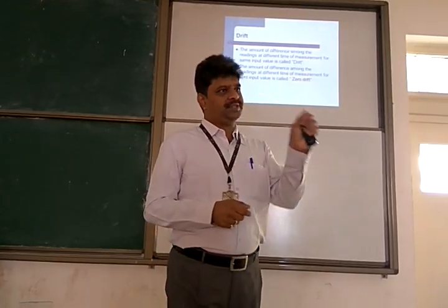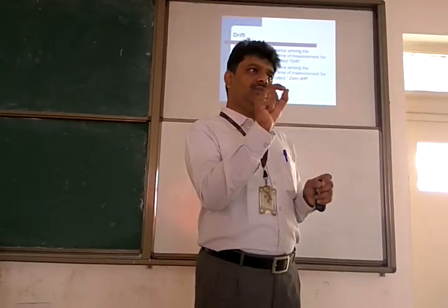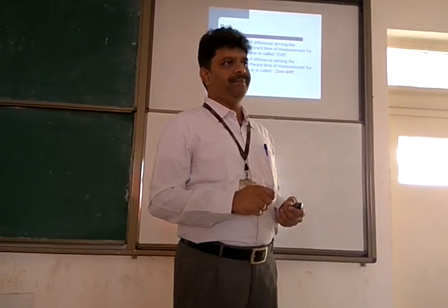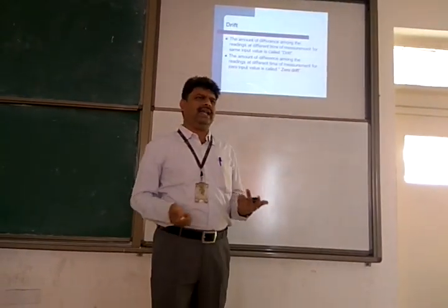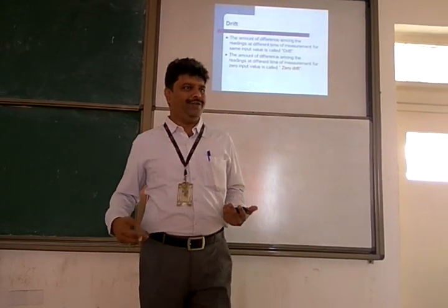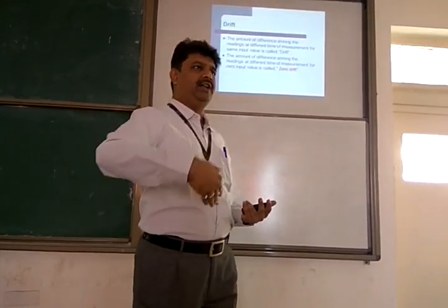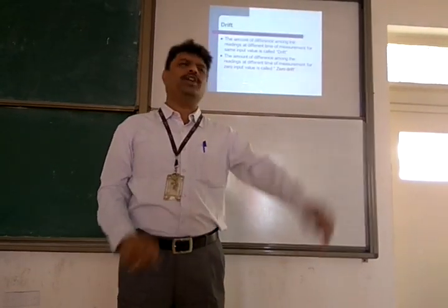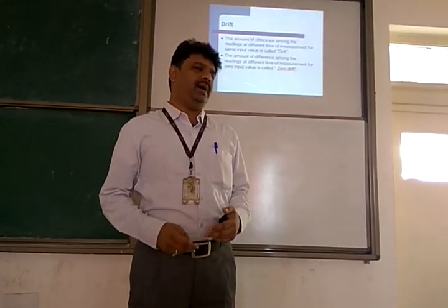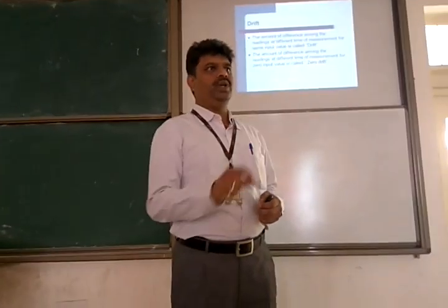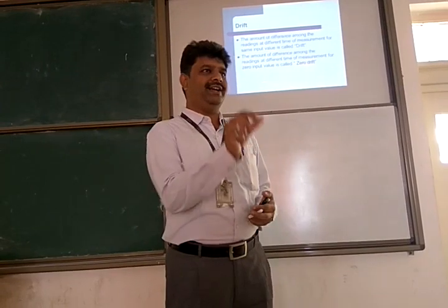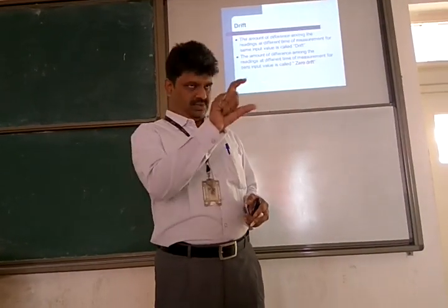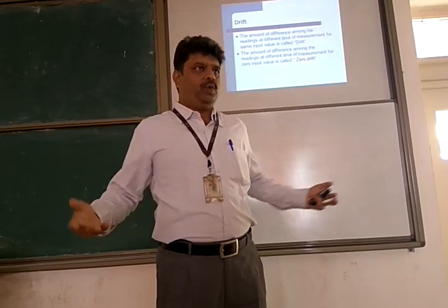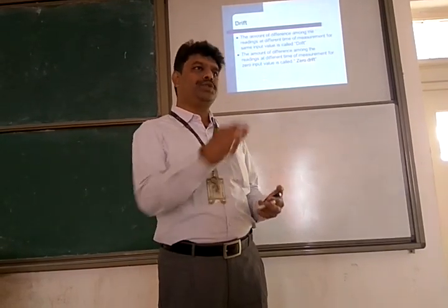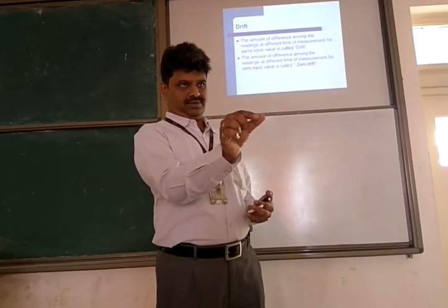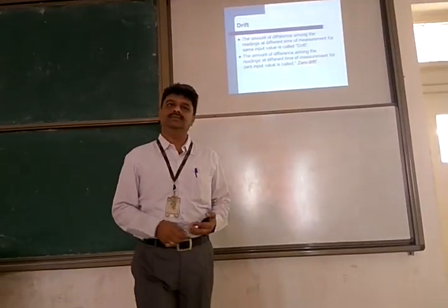It's only an adjustment in the zero setting, so that before you start using it, you just set the zero. We can call it a calibration at zero value, because you give some input value, you are correcting the output value and establishing the correct relationship. Nothing wrong in calling it calibration. But in commercial terms, we call it zero setting. If you go to a company and say, I am calibrating it now, they will laugh at you. Theoretically it is right, but when you talk among learned people, you should use the right term. So you should say, I am doing zero setting. I'm setting it back. We stop here and then we continue.